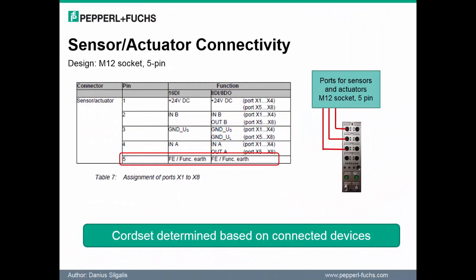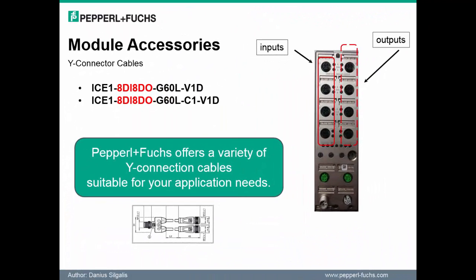There is an important point regarding sensor and actuator connectivity. As noted on the slide, pin 5 of the module must be left available for earth ground. So as you are making your selection of devices to connect to the module, be sure pin 5 is not being used for other needs. The Ethernet IO block has 8 ports available; however, we have the ability to connect 16 devices to a single module. Pepperl+Fuchs offers a variety of Y-connection cables suitable to allow for a higher quantity of devices to be connected. A product selection document is available to list all the available accessories to make this possible.